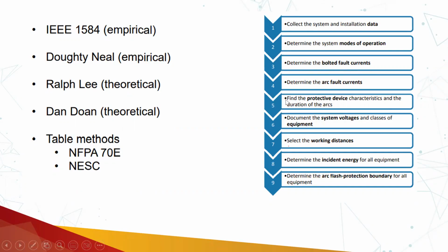Determine the bolted fault current, determine the arc fault current. So first you are going to find the maximum short circuit current, and based on that maximum short circuit current, what will be the arc fault current. The arc fault current is always lesser than the bolted short circuit current due to the additional resistance of the air medium through which the arc fault actually develops.